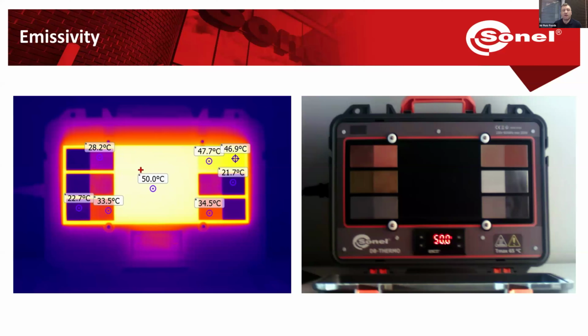Now, in case we set the camera incorrectly with the value of 0.2 for the emissivity, then for the same object and same conditions, the camera will present the temperature of our object as 20 degrees. So this can cause a very big measurement inaccuracy. In the example on the picture, you can see our demo board. The temperature of the demo board is 50 degrees, and it has some black material in the middle, just to avoid any reflections. Then the emissivity here can be set to 1.